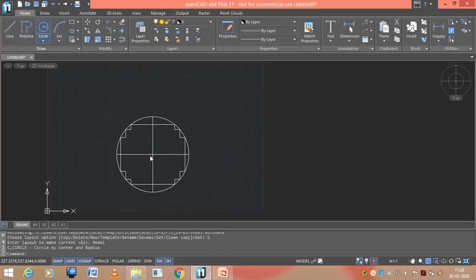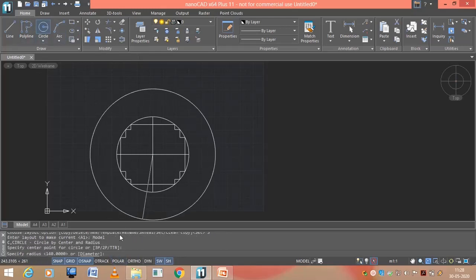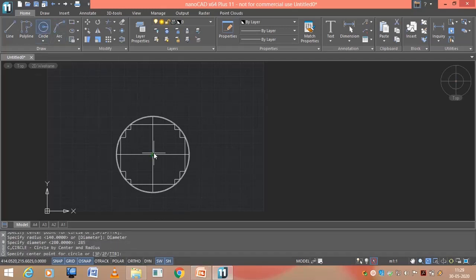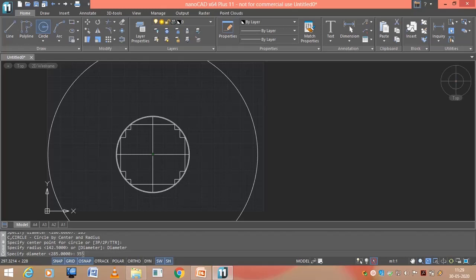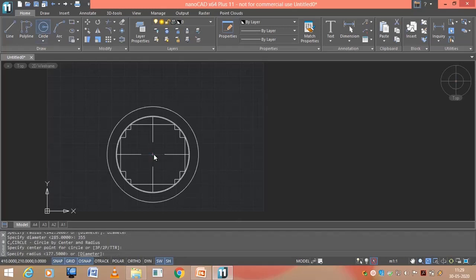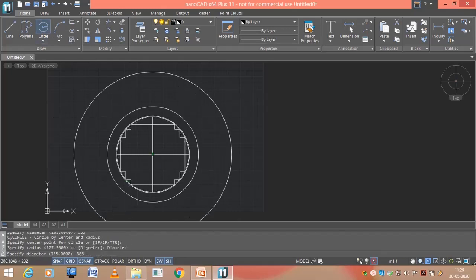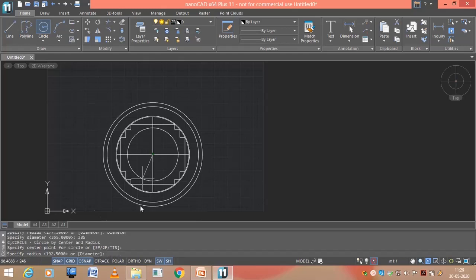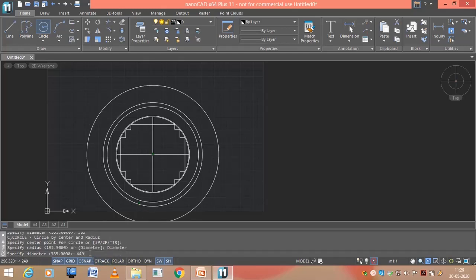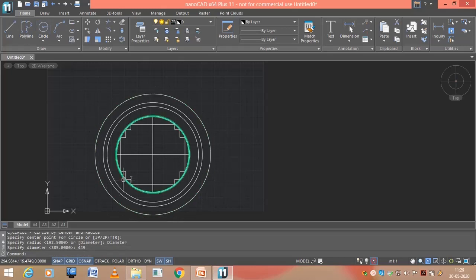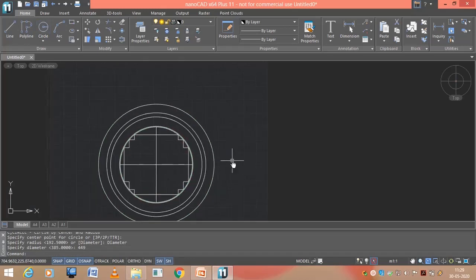So this should be covered with LV winding, right? The LV inner dia we have calculated is 285 mm, it is a diameter. Then the LV outer dia, then HV inner and then HV outer. HV inner is 385 and HV outer is dia 449 mm. Right, so this is your sectional plan of one limb in a 3-phase core type transformer.